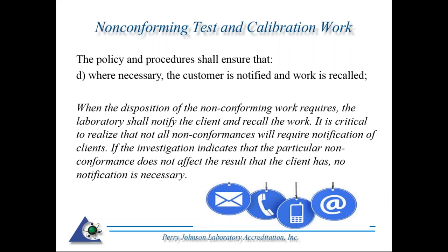If the investigation indicates that the particular nonconformance does not affect the result, then no client notification is necessary. Hence, if I was an assessor and it was an instance where nonconforming calibration or testing work was performed, I'd be looking for the investigation, and how it was determined whether or not the particular nonconformance, whether it was the out of tolerance condition of a piece of equipment that was calibrated, or perhaps quality control charts being out of limits, impacted the customer's results. And if it did actually impact, then customers being notified, and if necessary, the work recalled.